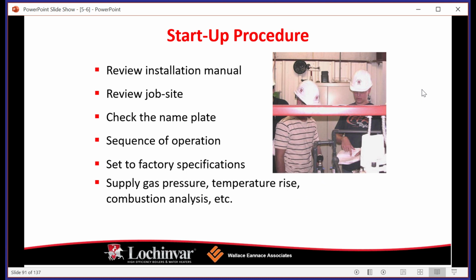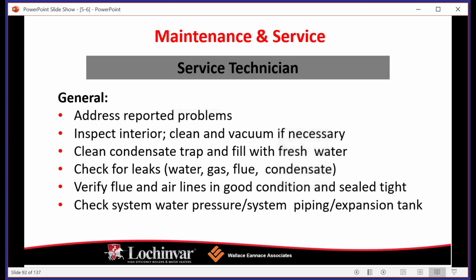As a former mechanic, you know, we would get calls and all you get is, oh, it's broken. So now you're driving out in your truck at 11 o'clock on Friday night, and you're like, well, what could it be? Do I have an igniter? Do I have a flame rod? Should I bring my manometer? Well, the answer to all 3 questions is, yeah, you should have them. But it gives you the ability to forecast, right? You have that remote access and you can see what the boiler's doing. You can see what's happening to it.